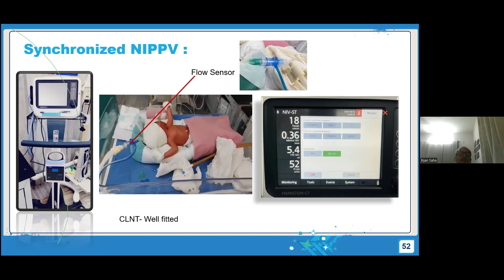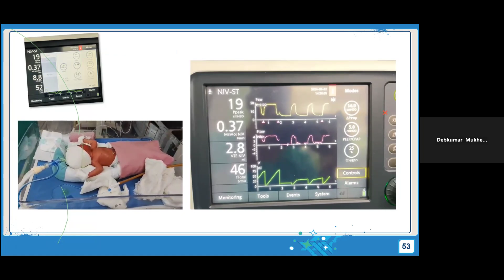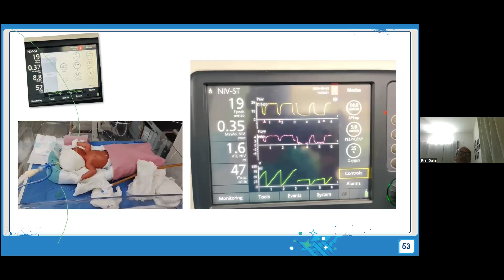Just see this baby is breathing, and you see there is some triangle. This triangle means these are all synchronous breaths. But what we have seen with Hamilton also, this Hamilton uses the pneumotachometer as the flow sensor. If there is some condensation, you may get this triangle. So whenever you see this triangle, don't be sure that these breaths are actually synchronized. If there is some condensation in the circuit, it will show like this. But this baby is a little bit bigger baby, that's why he is synchronizing. So for synchronization, in our hospital, the machines we have are Hamilton and Optimatics.